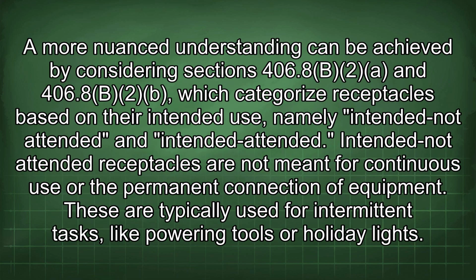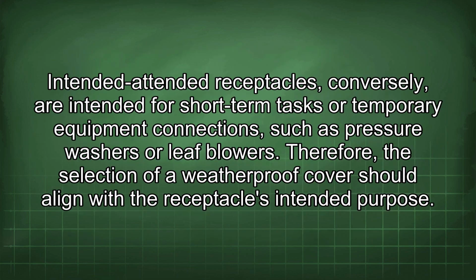A more nuanced understanding can be achieved by considering sections 406.8(B)(2)(a) and 406.8(B)(2)(b), which categorize receptacles based on their intended use, namely intended not attended and intended attended. Intended not attended receptacles are not meant for continuous use or the permanent connection of equipment. These are typically used for intermittent tasks like powering tools or holiday lights. Intended attended receptacles, conversely, are intended for short-term tasks or temporary equipment connections such as pressure washers or leaf blowers.